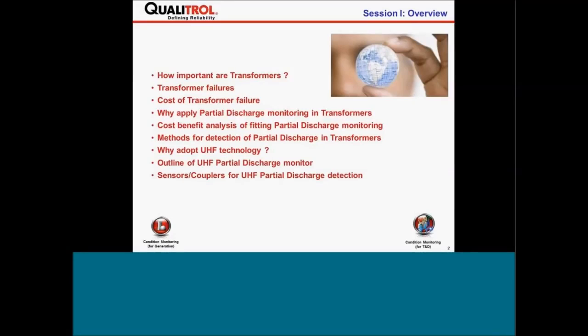That leads us on to the fact that a large number of the defects are first seen by partial discharge, and this can allow us to detect before failure can happen by detecting the partial discharge.